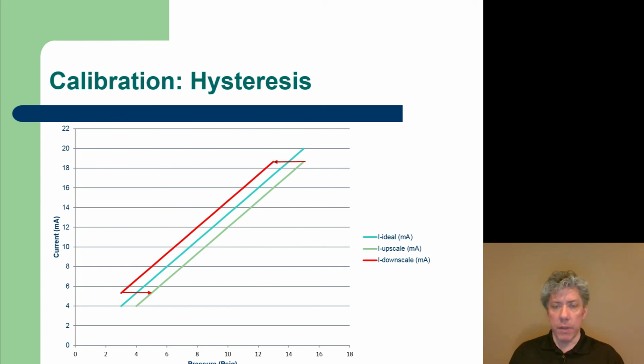Now, valves have hysteresis, current to pressure transducers have hysteresis, most things do, and all that really means is that the input-output characteristics depend on whether the input is moving upscale or downscale. The output will be different depending on whether the input is increasing or decreasing. So in the case of a valve, as the pressure increases, pushing the stem farther into the valve, you'll get a different flow than when the pressure is being released and backed off, going downscale, and pulling or allowing the stem to come back out of the valve. You'll get different flow rates even though you might be at the exact same pressure.